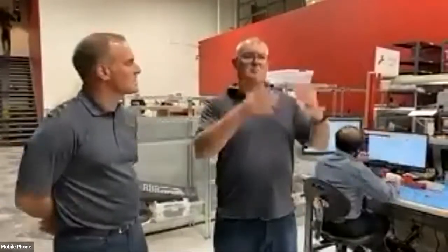That's right. We get the instrument back at the second to last stage in the process. The instrument will come out of the lab and come back in for final test. Final test is when we connect the instrument back up to Ruskin. We check that the calibration coefficients on the printed certificate match the coefficients in Ruskin. So we know the instrument is going to work properly.